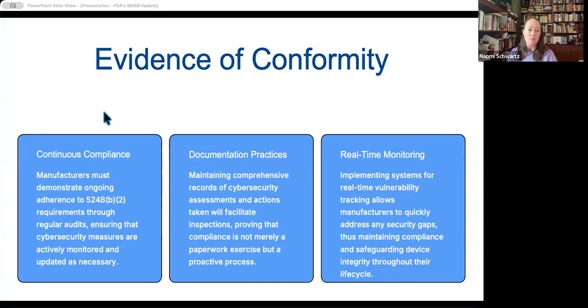What evidence are they looking for? And now we're going to apply that stricter definition of 524B applies. You're a cyber device. Your product has been reviewed by FDA and submitted subsequent to March 29th. You have continuous compliance expectations. You should be demonstrating ongoing adherence to the 524B(b)(2) requirements. That's through regular internal audits, ensuring your cybersecurity measures are active and monitored, and that you're following those metrics that FDA's pre-market guidance calls out, and that you're able to track how often are vulnerabilities appearing, how quickly can you disposition them, how quickly can you patch them if they require patching. What are your risk acceptance criteria?